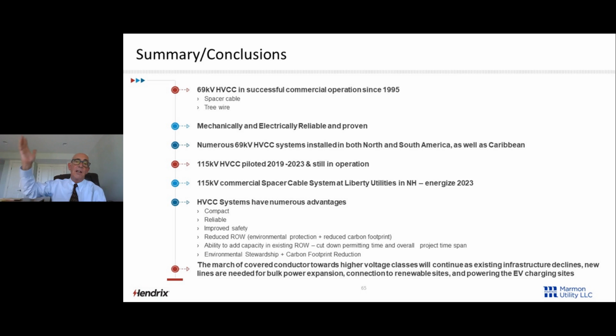Conclusions, basically: 69 kV high voltage covered conductors have been in successful operation for a long time, since 1995, both spacer cable and tree wire. It's mechanically and electrically reliable and proven. We've got 69 kV high voltage covered conductor in North America, Canada, South America, and the Caribbean. Our 115 kV pilot is almost 4 years old, still in operation. Our 115 kV system at Liberty Utilities is going to be energized, if it's not already energized.